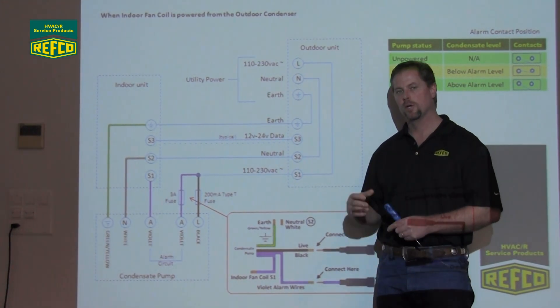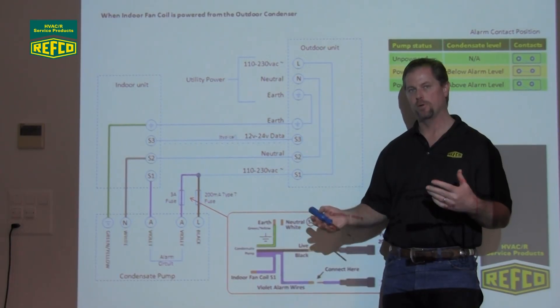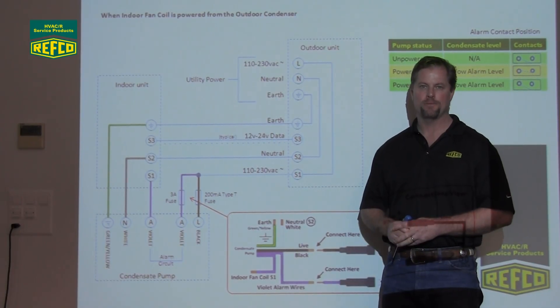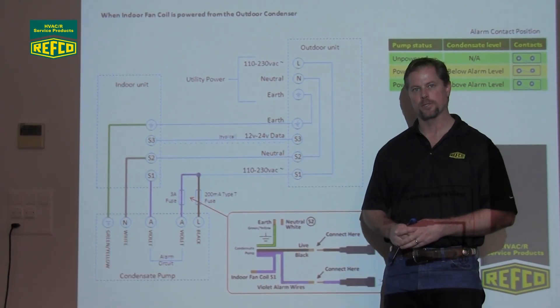This is the other way to wire it if your indoor unit is powered from your outdoor condenser. There's another way to do it, which is when your indoor unit and your outdoor unit are powered separately — on those, you're just going to land your live and neutral to the respective live and neutral on the indoor unit to power your pump. On behalf of everyone at REFCO, we want to say thanks for watching and we appreciate your business. Thank you.